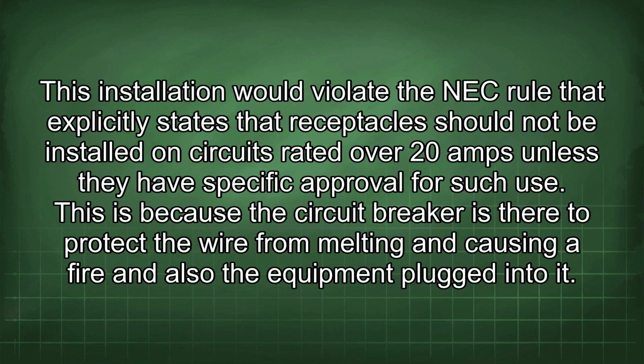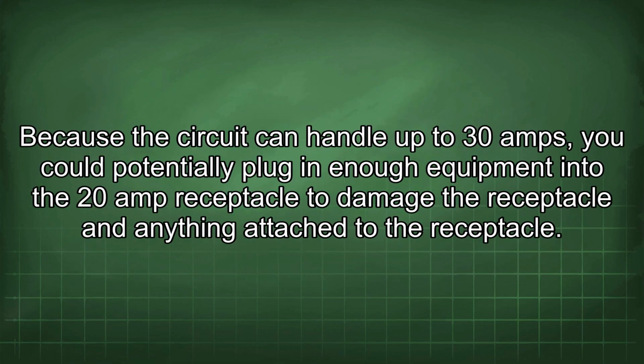This installation would violate the NEC rule that explicitly states that receptacles should not be installed on circuits rated over 20 amps unless they have specific approval for such use. This is because the circuit breaker is there to protect the wire from melting and causing a fire, and also the equipment plugged into it. Because the circuit can handle up to 30 amps, you could potentially plug enough equipment into the 20-amp receptacle to damage the receptacle and anything attached to it.